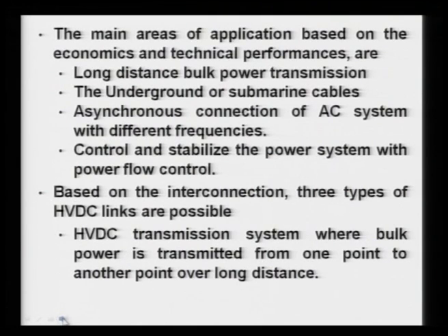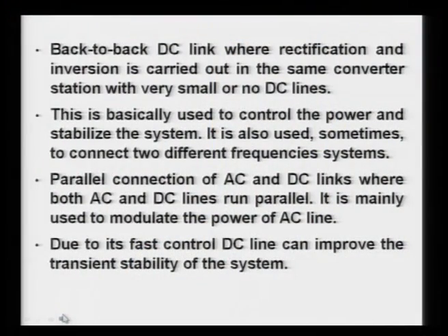So, I can summarize the HVDC application again: based on the interconnections, three types of HVDC links are possible. One is the HVDC transmission system, where bulk power is transmitted from one point to another over a long distance. Another application is back to back connections, where rectification and inversion are done at the same place or very near to each other, and the major concern is to control the power from one region or area to another.